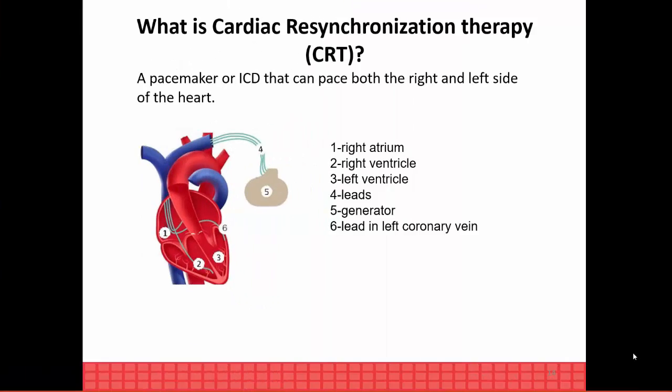So we talked about an ICD, and now I just want to introduce you to the cardiac resynchronization therapy device, which is a heart failure device. This is unique because we want to pace both the right and left ventricle. And I want to bring your attention to number 6, and this is the lead on the left side of the heart. It is not inside the heart, it's actually sitting in the left lateral vein.